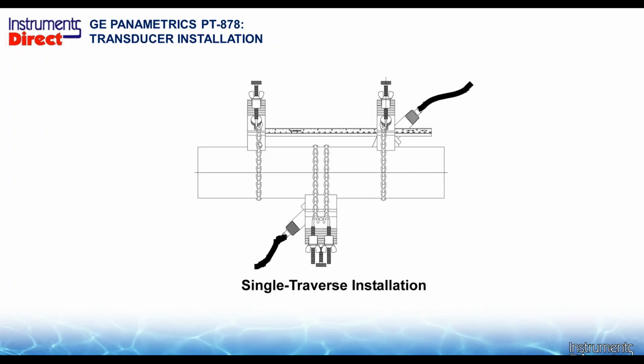So same thing with the Z configuration. The second reason you don't want to do it is it's not as fun to install because you can't see the other side of the pipe there. So you try V all the time until you can't get it to work, and then in the larger pipe size, you don't have an opportunity. What I do when I have a large pipe application, I mount one transducer on the side of one pipe about 3 o'clock. And so what I do, in this case there, I draw a line across the top of the pipe until I find my 180-degree line on the other side, draw a line from here to here. Then we measure the spacing from this point to this point. We draw another line there, and that's where you can strap on your mating transducer.